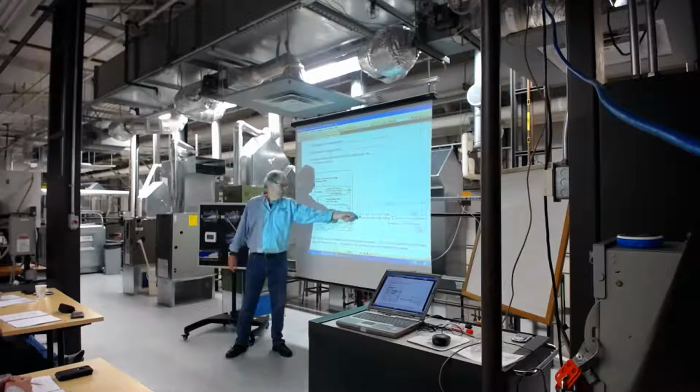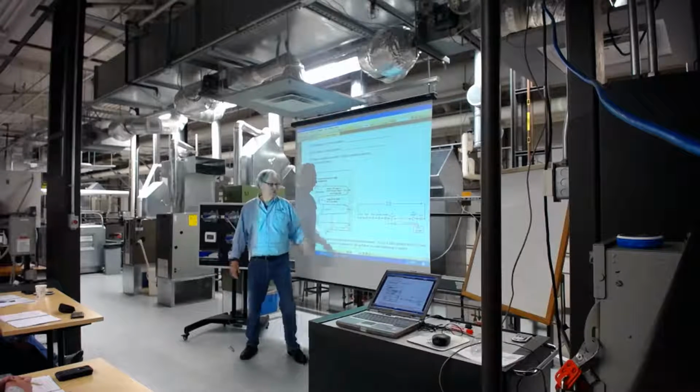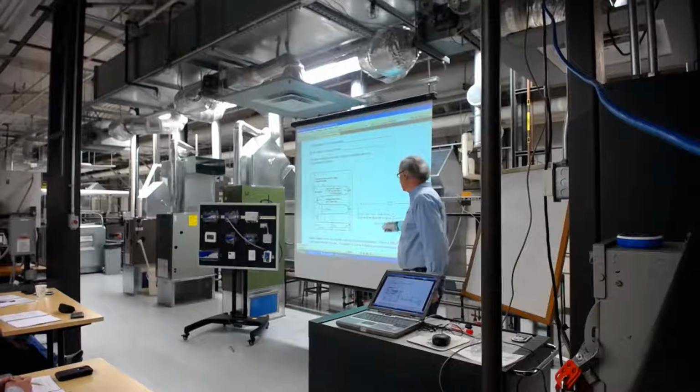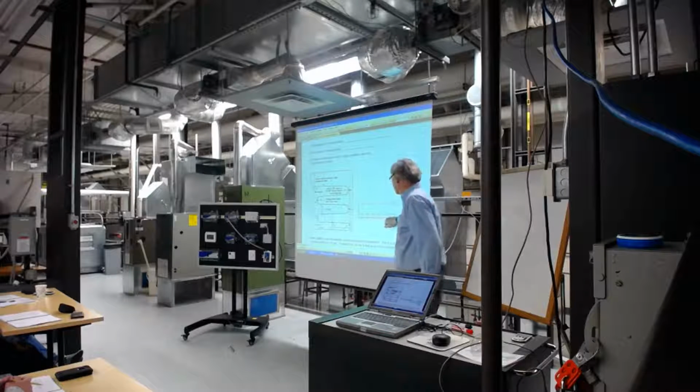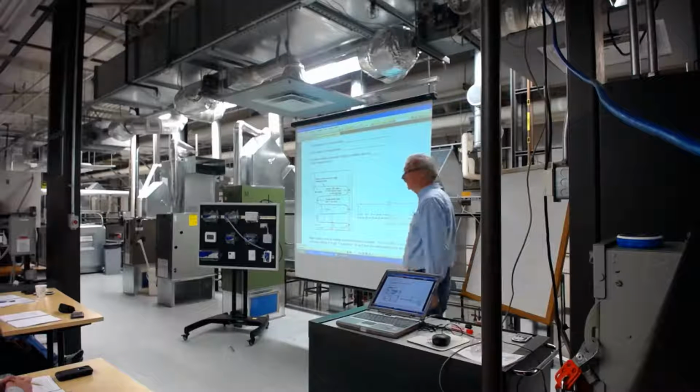So here we've got your low limit. These could be pressure switches. These are extra safeties that are in there. So this whole thing, along this leg, is all safeties. Smoke detectors on the supply side, smoke detectors on the return side. Always normally closed contacts. Here's your HOA, and right now, it's set up to be in the auto position. In series with that is the relay from the controls. All it is is a set of contacts. It's a relay, right? Single coil contact.